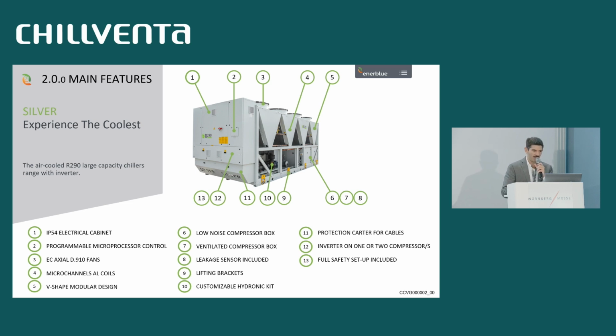The compressors are closed to make the unit relatively silent. Otherwise, the noise would be too high, also for the norms. As mentioned, the unit is filled with propane, so flammable refrigerant. So the unit is equipped with all necessary equipment to prevent risks, like the extraction fan, ATEX extraction fan in the compressor room. A gas sensor to detect a possible leakage also in the compressor room. And ATEX components like the compressors in the compressor room. The unit is also equipped with small brackets to lift it with a crane.